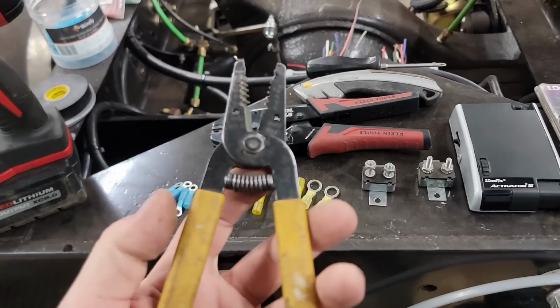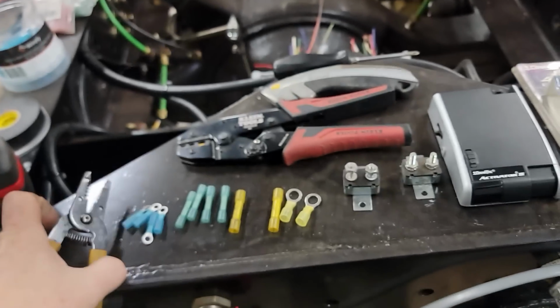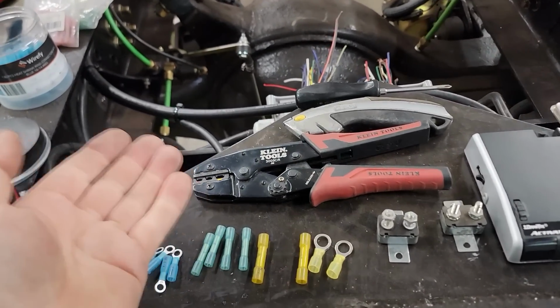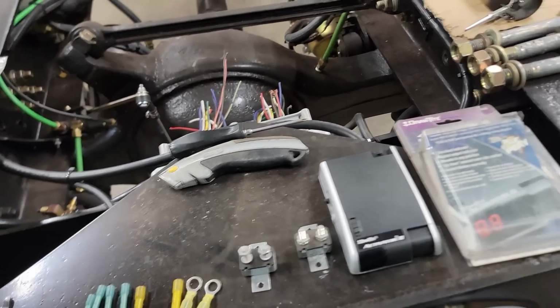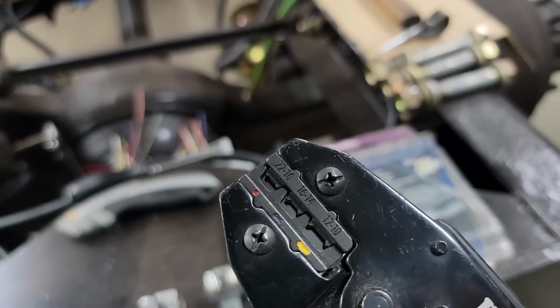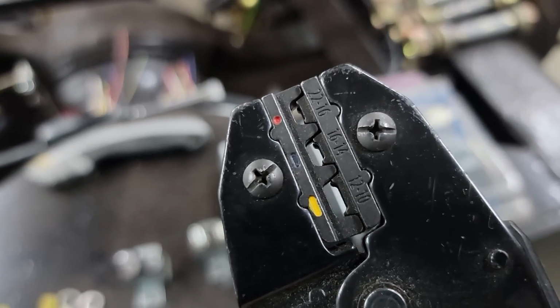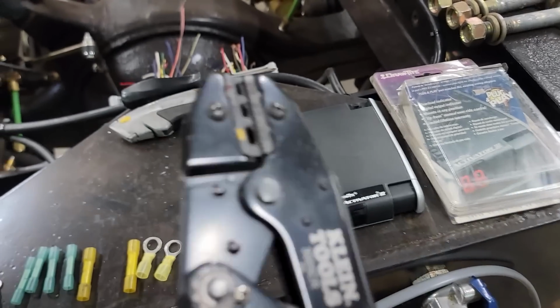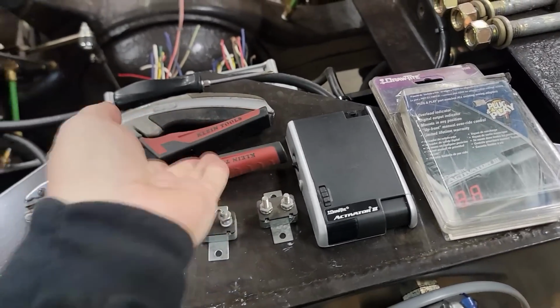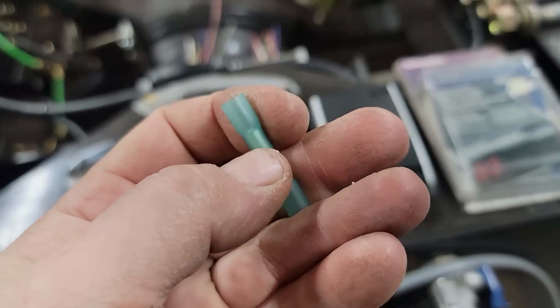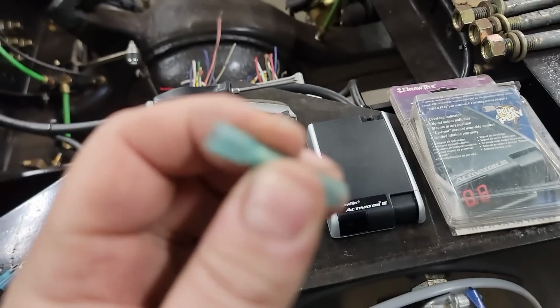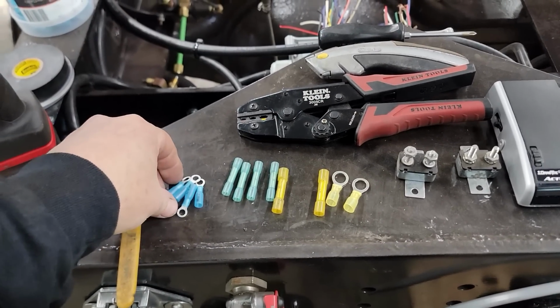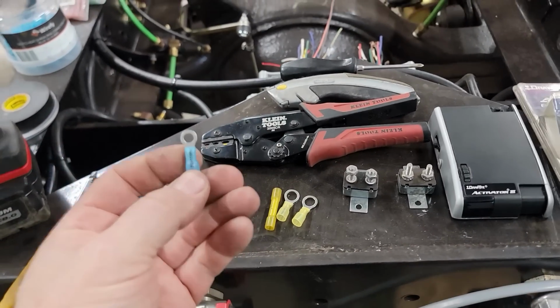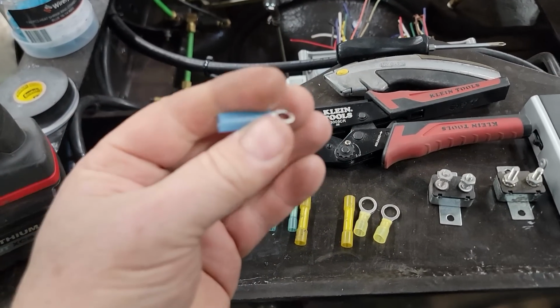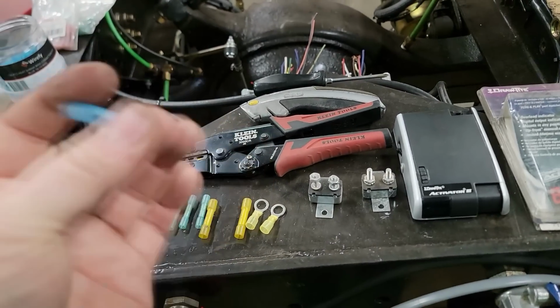We need a good set of strippers, nice and sharp, that will go up to 10. And then if you're going to use these, you need to use the proper crimp tool. This tool is made by Klein, and you see the color indications on here. And you'll notice there's no teeth in there. This will make a flat crimp instead of using a crimper that has a spike that pierces the insulation, rendering your heat shrink connector now not weatherproof or something similar to that. Even though my preference is to crimp, solder, and heat shrink with deox, I'm just going to use these so you guys can see exactly how it can be done.